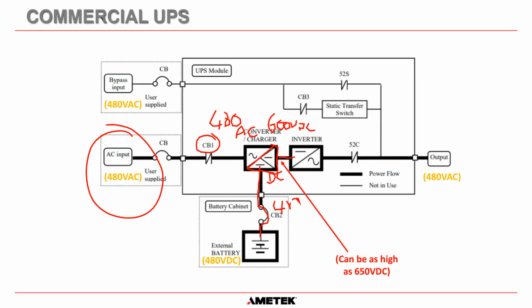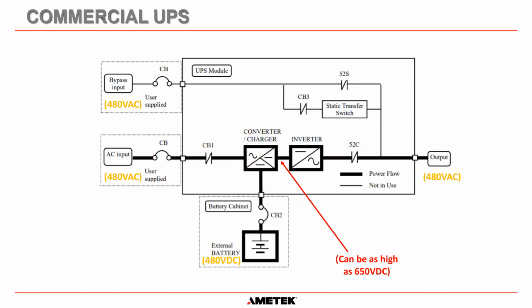Okay, and then that DC goes into the inverter. The inverter converts that DC into AC, and then on the output we have this contactor. Okay, and in normal operation it's normally closed, and power will flow out that way. And then on the static transfer switch, we have a contactor here as well, and then a circuit breaker here. So if the inverter output fails, the static transfer switch will immediately take this 480 volts out through the static switch and out to the output. But the static transfer switch is only rated to do that for a very small period of time. And what it does is, as soon as the static transfer switch, which is the SCRs that have no moving parts, has transferred the load, it will then pull in contactor 52S, and it will allow the power to flow through that way, and then this transfer switch turns off.